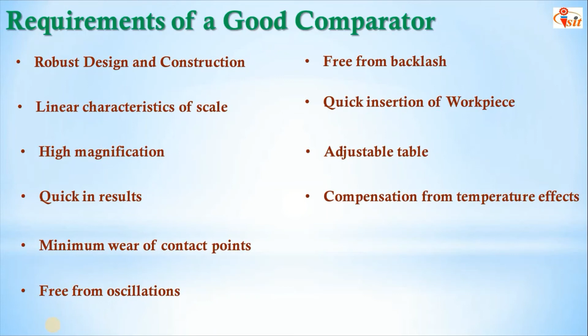Quick insertion of workpiece: means should be provided for lifting the plunger for quick insertion of work. So we can easily insert the workpiece and check the pointer movement. Adjustable table: the table of the instrument should preferably be adjustable in a vertical sense. Compensation for temperature effects: the indicator should be provided with maximum compensation for temperature effects. So there will be no variation due to temperature change or environmental change.